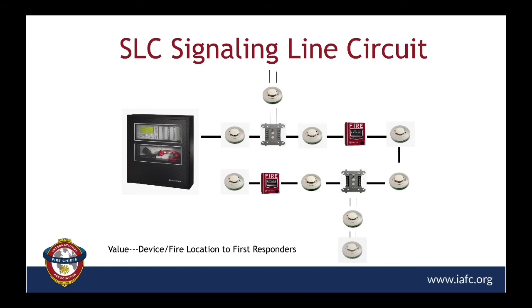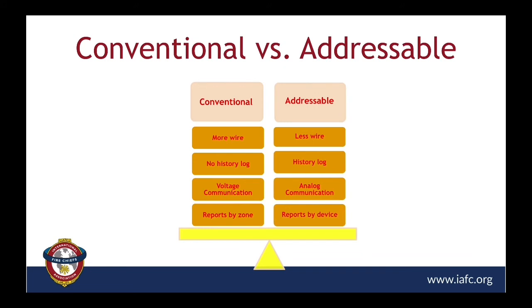And the nice part is when you walk in the door and look at that fire alarm panel, the display on the front of the panel is going to tell you that it's smoke detector 1-10 on the first floor in Chief O'Brien's office. It's going to spell out exactly where that device is located. And that obviously is the biggest benefit for the first responder, to determine where the fire is originating. And as things build in a real fire situation, you're actually going to be able to see the spread of fire through the building by watching how the different devices get activated.